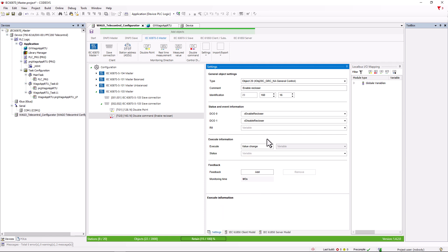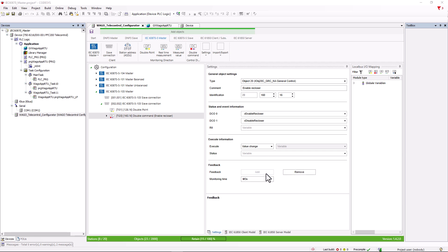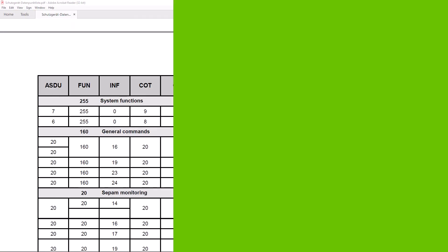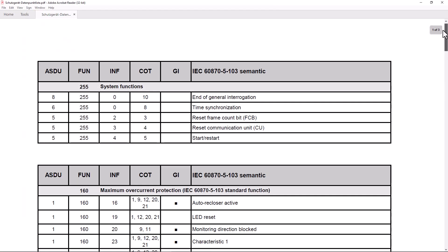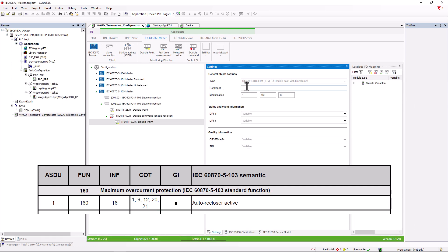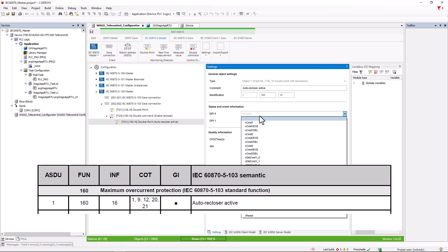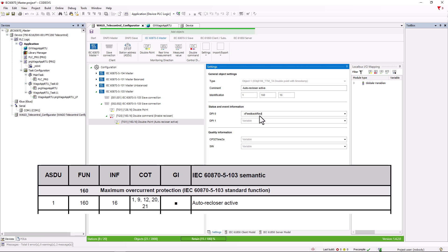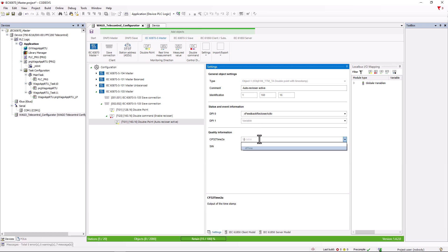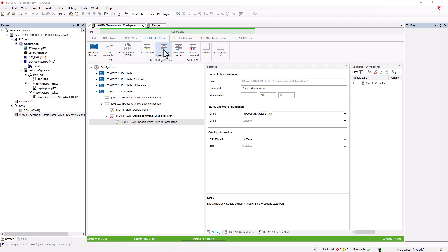As already mentioned, the master expects an answer to a command which we can add with this button. In our case, the response is that the auto recloser is active. We adopt the comment and the identification. And here we have the case that the manufacturer of the protection device only returns one bit. So we only assign a variable for dpi zero. Here we can specify a variable in which we will have the timestamp in the form of CP32, hour, minute, millisecond. In the same way, we can create a single measured value with a real-time measured value.